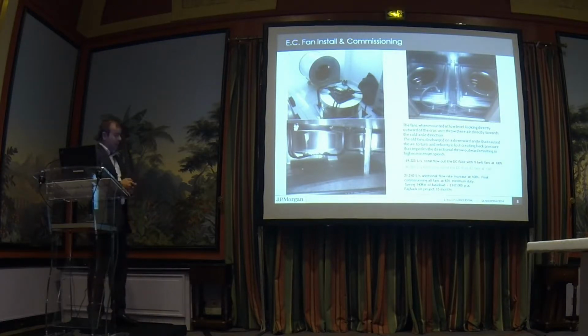So these are the old fans we took out there. Whopping great big thing. It used to run at about 0.6 power factor, which is pretty bad. Once we put these in, we can run about 0.98. So the kVA just dropped considerably.